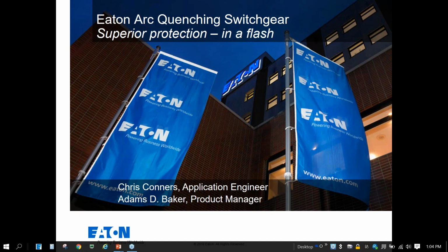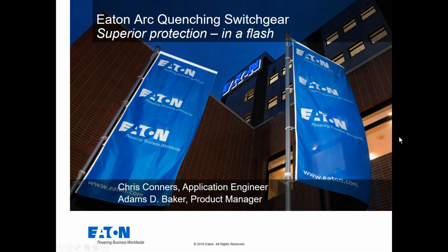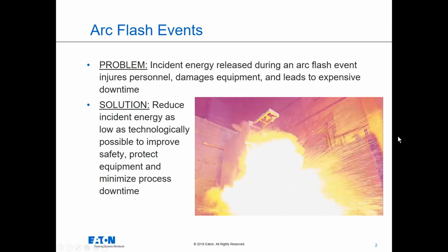On the front end, what I'd like to do is discuss what the current state of arc flash is and how that problem presents itself. So when we discuss arc flash, since NFPA 70E was released in 2002, the conversation has grown, the engineering controls have gotten better, and the technological solutions presented by equipment manufacturers such as Eaton have increased in number, type and definition. But all of those are trying to fix one problem: reduce the incident energy as low as technologically possible to do many things. Obviously improve the safety around the equipment while it's operating, and then of course to protect the equipment and minimize process downtime or losses to the system.